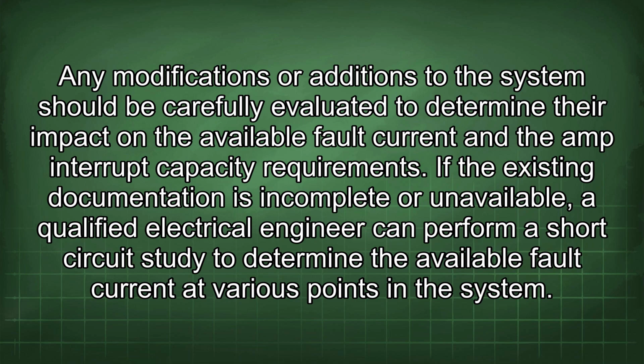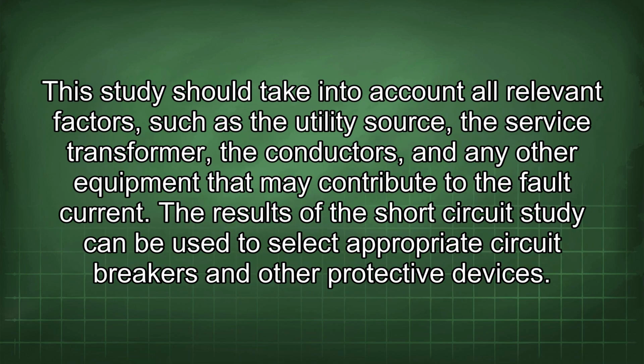If the existing documentation is incomplete or unavailable, a qualified electrical engineer can perform a short circuit study to determine the available fault current at various points in the system. This study should take into account all relevant factors such as the utility source, the service transformer, the conductors, and any other equipment that may contribute to the fault current. The results of the short circuit study can be used to select appropriate circuit breakers and other protective devices.